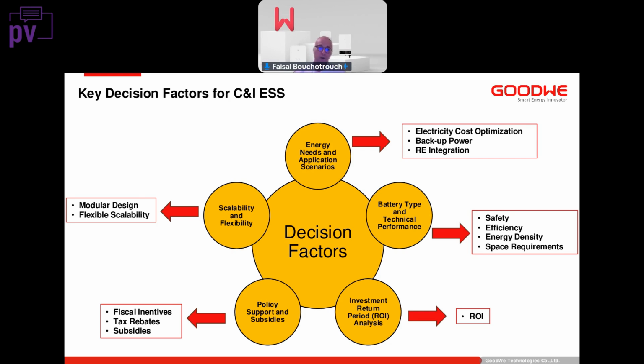First, we need to identify our energy need and application scenario. This is the basic thing to start with. If the primary goal is to reduce electricity costs, the storage system's capacity and efficiency will directly influence the economic benefits. Typically, systems in the 50 to 500 kilowatt hour range are suitable for businesses with significant electricity price fluctuation, helping them perform peak shaving and load balancing. For critical infrastructure, the storage system capacity should be around 1.5 to 2 times the company's electricity demand, to ensure continued operation during outages. This should be considered case by case due to the criticality of the business itself.